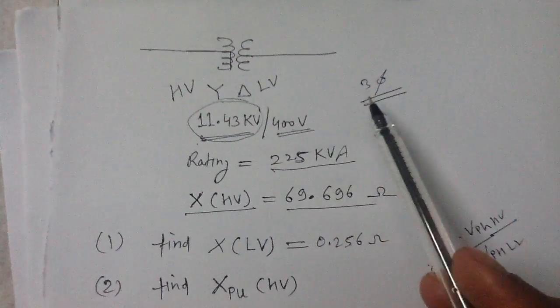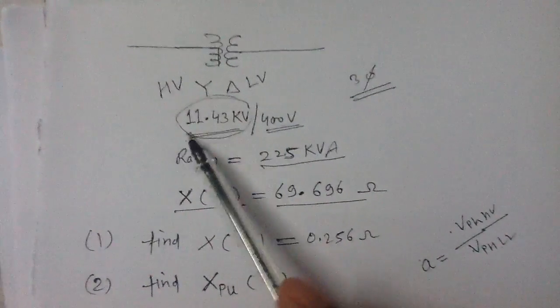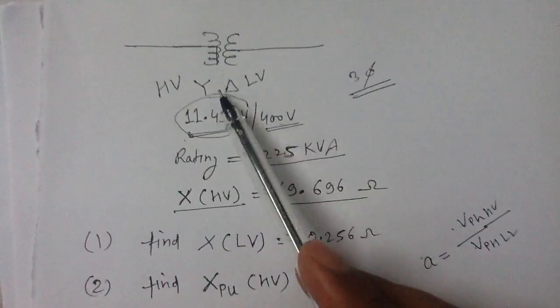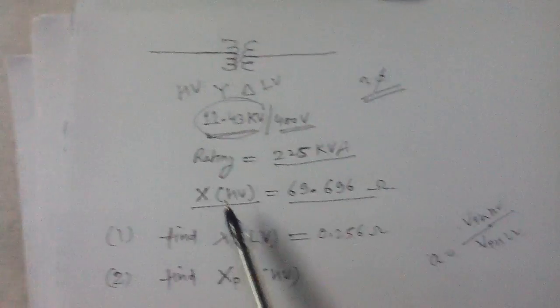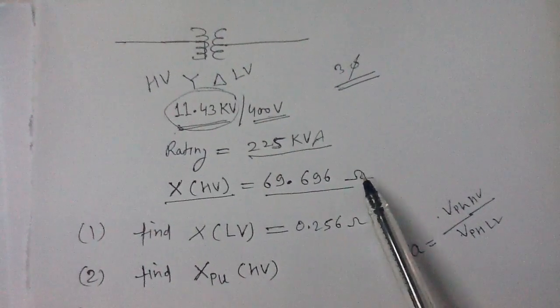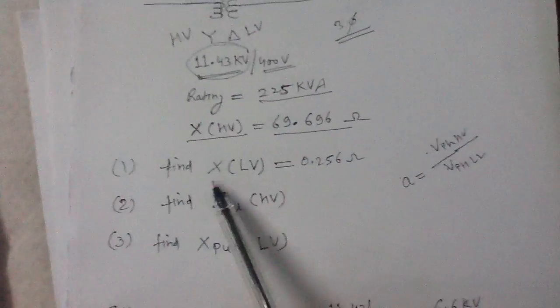This is a very important problem involving a three-phase transformer. The rated values of the transformer are 11.43 kV by 400 volts. The HV side is connected in star and the LV side is connected in delta. The voltages given in three-phase transformer ratings are line-to-line voltages. The second rating is 225 kVA, and the per-phase reactance referred to the HV side is 69.696 ohm.